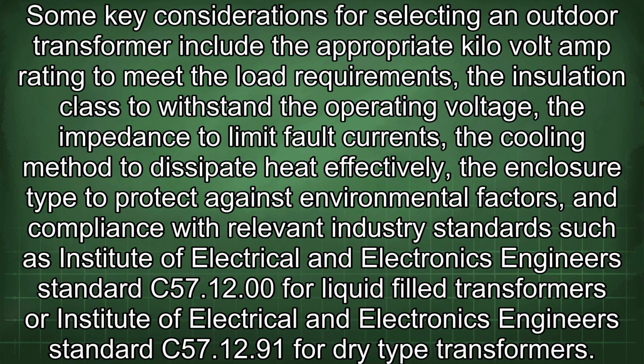Some key considerations for selecting an outdoor transformer include the appropriate kilovolt amp rating to meet the load requirements, the insulation class to withstand the operating voltage, the impedance to limit fault currents, the cooling method to dissipate heat effectively, the enclosure type to protect against environmental factors, and compliance with relevant industry standards such as Institute of Electrical and Electronics Engineers Standard C57.12 for liquid-filled transformers or Institute of Electrical and Electronics Engineers Standard C57.12.91 for dry-type transformers.